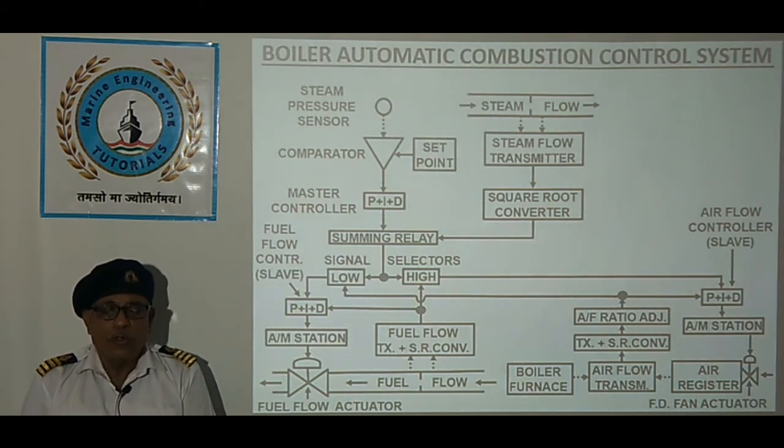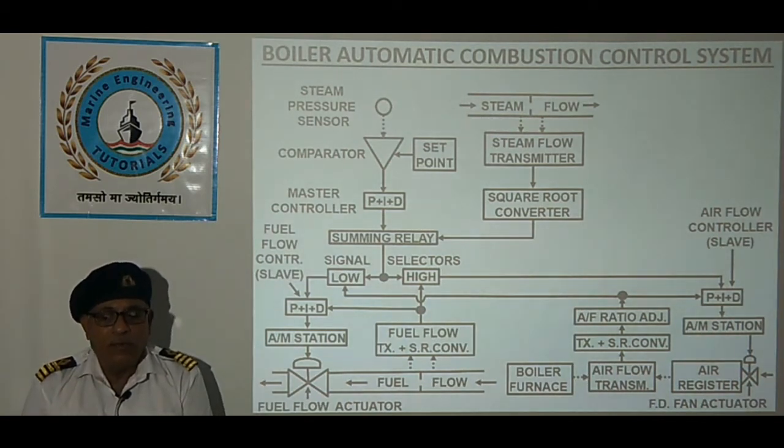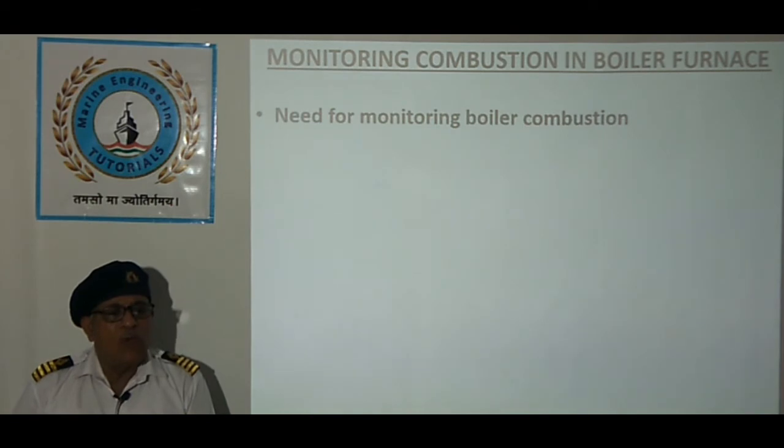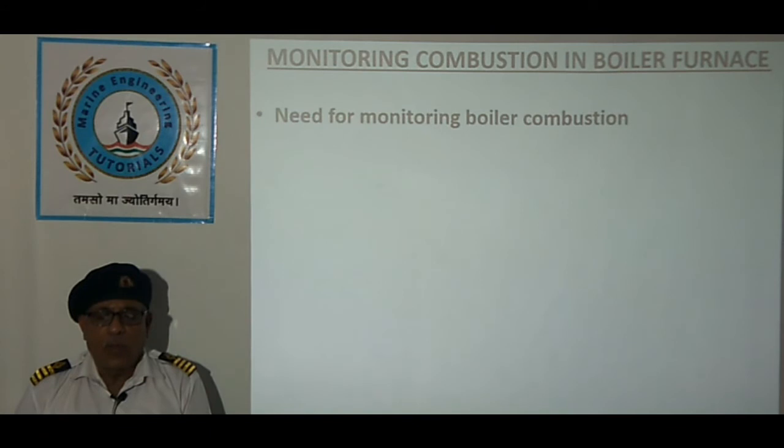When combustion control system is modulating at minimum load, steam pressure can be maintained by dumping excess steam. Now we will discuss methods of monitoring the combustion in boiler furnace. First of all, let us understand what is the need for monitoring the boiler combustion.